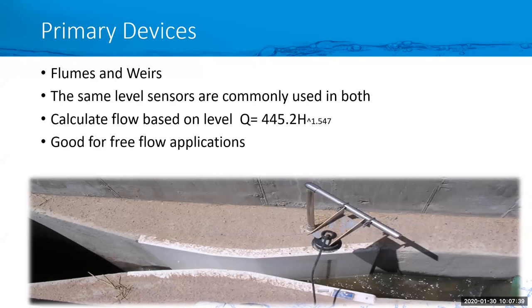Flumes are good for free flow applications because they have the assumption that the water is always going one direction, free flowing through the channel. It is unable to detect reverse flow. In a little bit, we'll talk about other options if you do have reverse flow. And if you have reverse flow through a flume, you do have bigger problems to worry about.